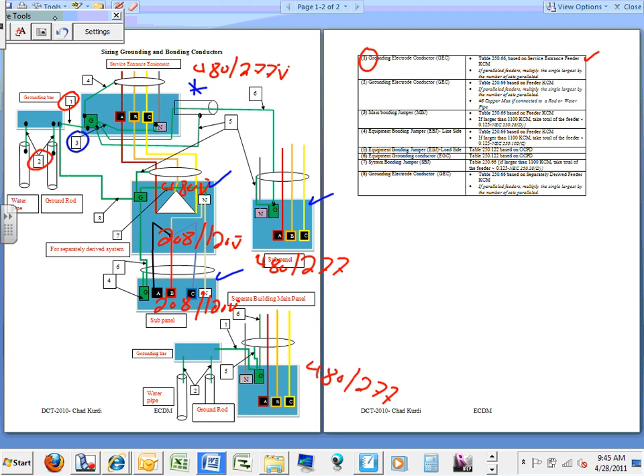Go to number three. Number three, guys, so that's number three. Number four here, can you guys see number four? Number four, this is a conduit. By the way, this right here is a conduit. Number four is basically bonding the conduit to the ground. You bond the conduit to the ground under certain circumstances inside the switch gear, because if you come from the switch gear, guys, it's not mechanically tied to the switch gear. It's open switch gear. So you bond it.